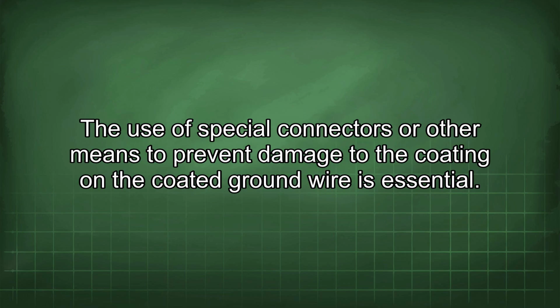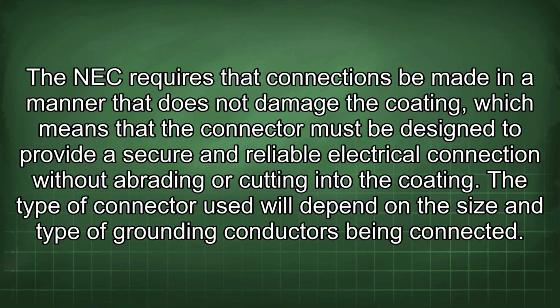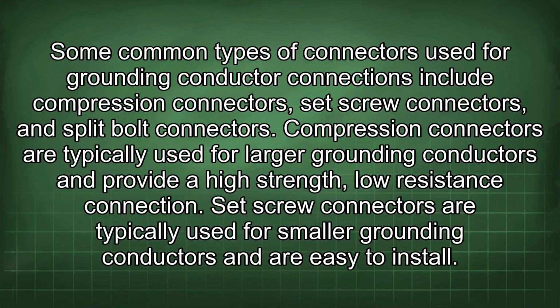The use of special connectors or other means to prevent damage to the coating on the coated ground wire is essential. The NEC requires that connections be made in a manner that does not damage the coating, which means that the connector must be designed to provide a secure and reliable electrical connection without abrading or cutting into the coating. The type of connector used will depend on the size and type of grounding conductors being connected. Some common types of connectors used for grounding conductor connections include compression connectors, set screw connectors, and split bolt connectors.